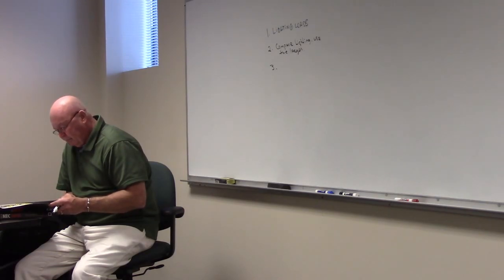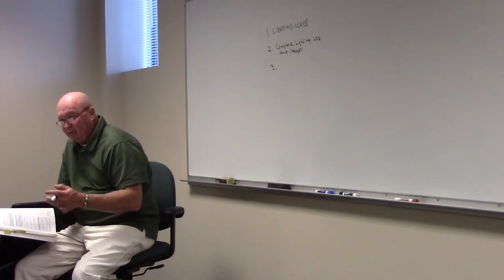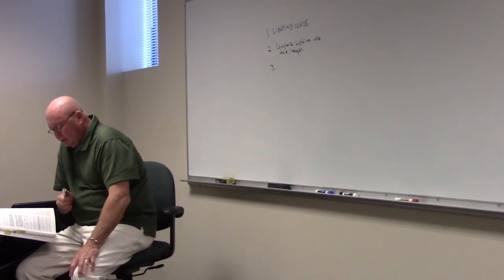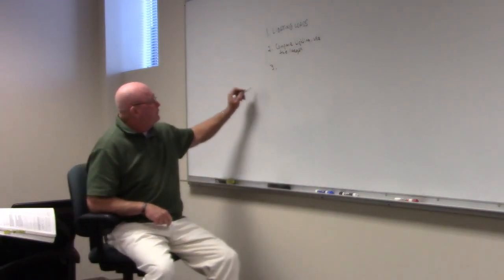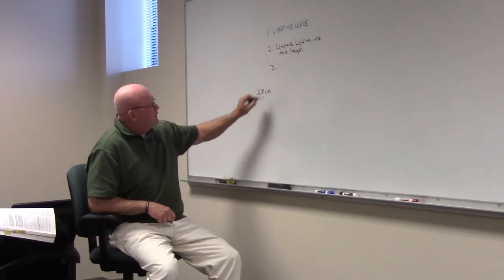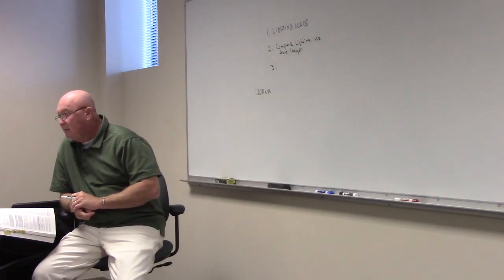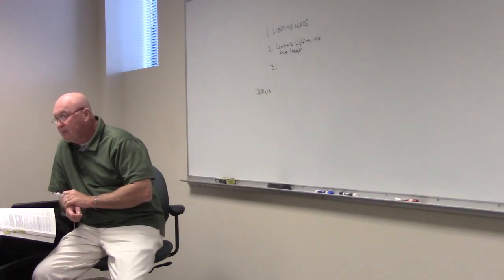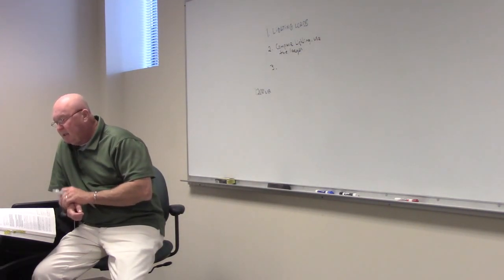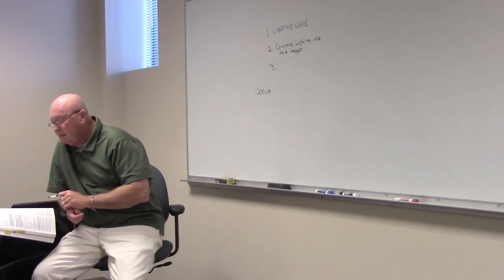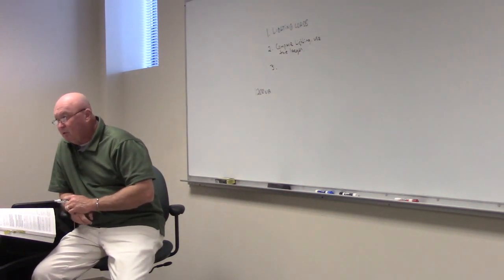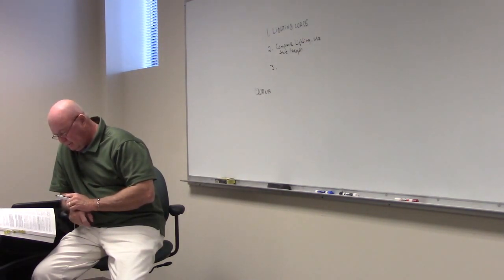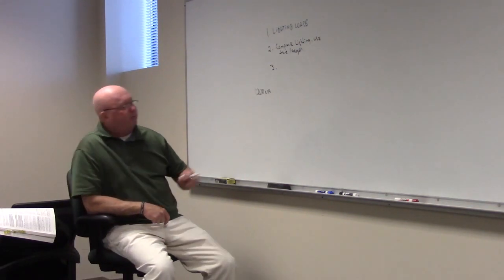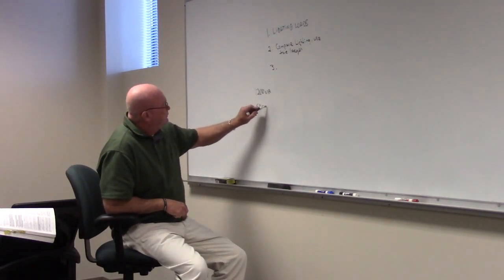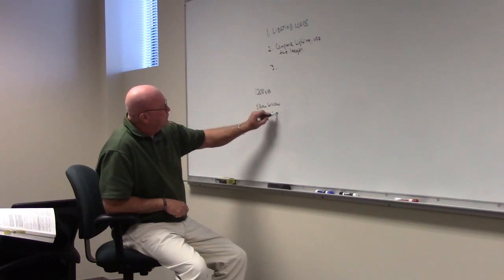If you look at F, it talks about signs. If you have a sign on the building, you have to calculate that differently. A sign is 1,200 volt amps. Am I right in saying that? 1,200 volt amps for a sign. In a commercial building, you're probably going to have that, aren't you? The other thing to consider is maybe if it's a store up front, you may have some show window lighting. If you look there at G, it's 200 volt amps per foot. So show window, 200 volt amps per foot.